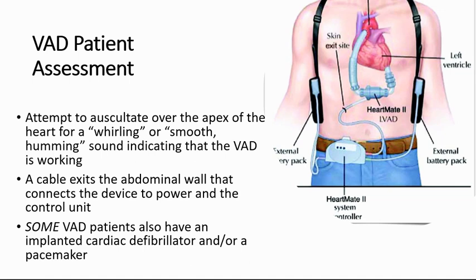Then you'll make sure the cable's not kinked, not crimped, not cut, all the way between the chest wall, or actually it's usually about the lower, the epigastric area, all the way to the controller itself. Make sure the power is plugged in, and so on and so forth.